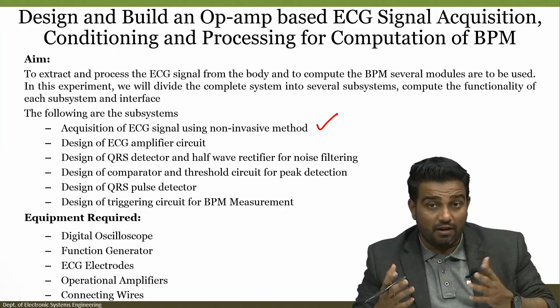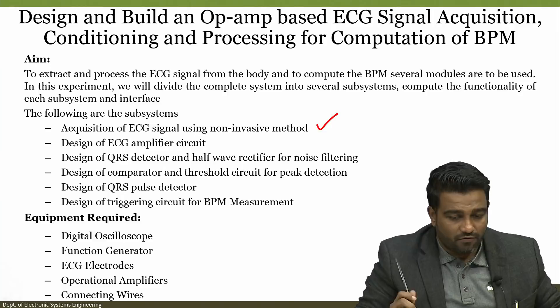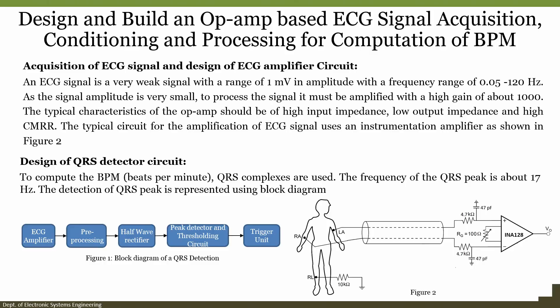The first subsystem is acquisition of ECG signals and design of the ECG amplifier circuit. An ECG signal is a very weak signal with a range of just 1 millivolt in amplitude and a frequency range of 0.05 to 120 hertz. Since the signal amplitude is very small, to process the signal it must be amplified with a high gain of about 1000. The typical characteristics of the op-amp should be high input impedance, low output impedance and high CMRR. The typical circuit for amplification of ECG signals uses an instrumentation amplifier.